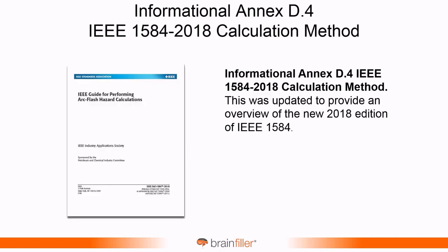Annex D, just a couple of final comments about the annexes. Annex D is where you had references to IEEE 1584 as well as a couple of other arc flash calculation methods. A big change with Annex D. What happened is, with the introduction of the new 2018 edition of IEEE 1584, we had to make some changes in the annex, because historically in Annex D, you could look at your 2018 edition and see this. Annex D had equations from a late 1990s paper. Those were some of the first empirically derived equations for arc flash. And then there were equations for the 2002 edition of IEEE 1584.